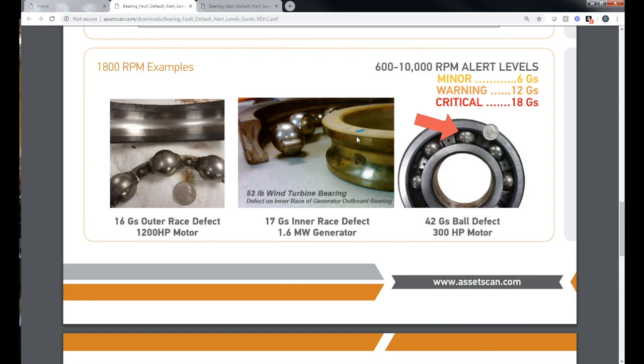On field inspection, they opened the bearing housing on the outboard of this generator. They noticed the grease had become discolored, turned black or dark gray, with metal debris. They took a borescope and were able to inspect the bearing, found this defect, and so knew with confidence that they could replace this bearing and remedy the problem. Again, providing that early or leading indicator allowed them to do the field inspection, confirm their plan, and schedule their repair.